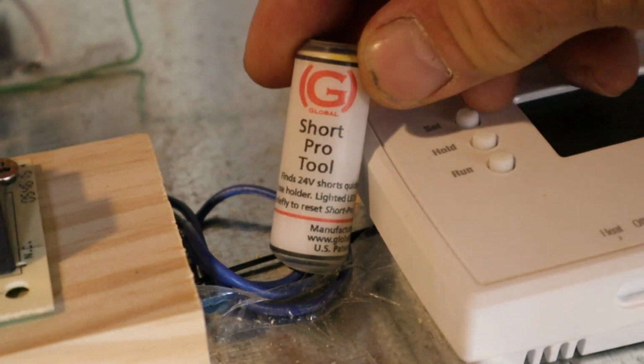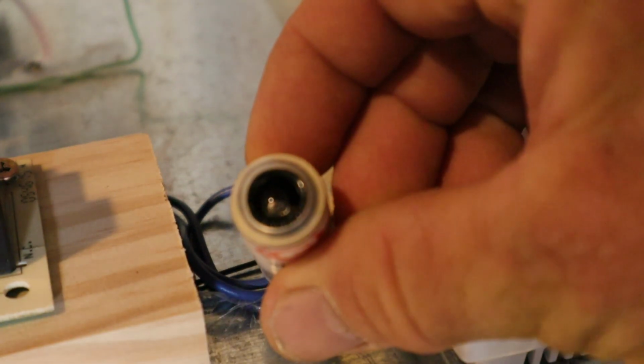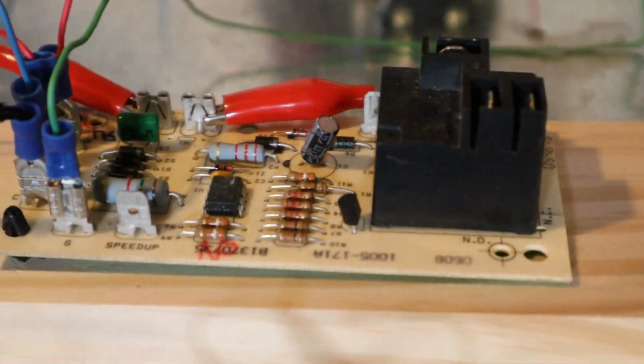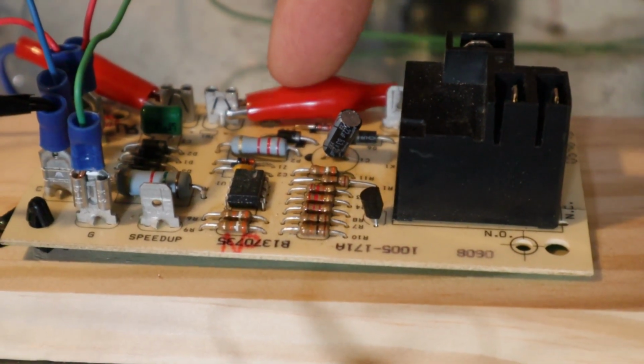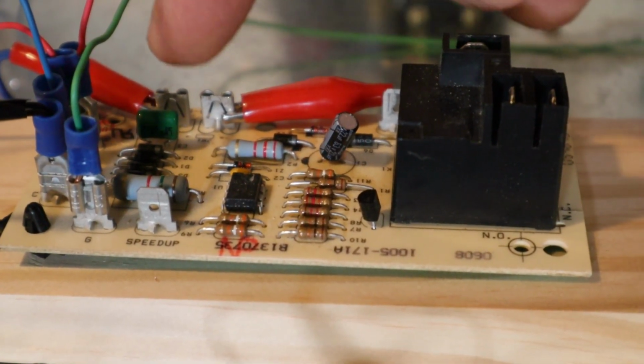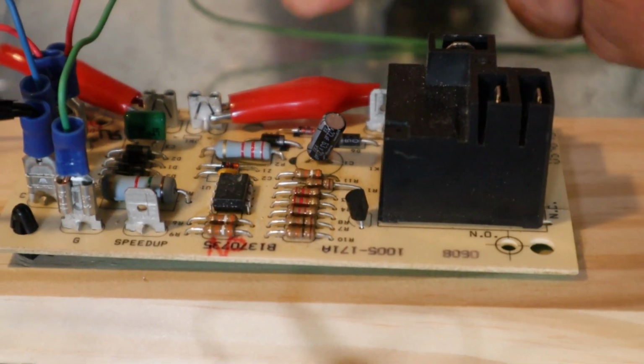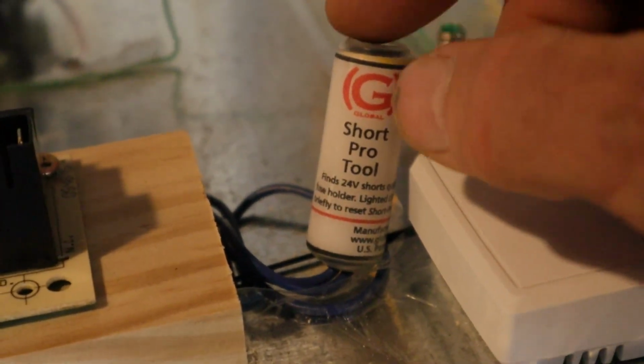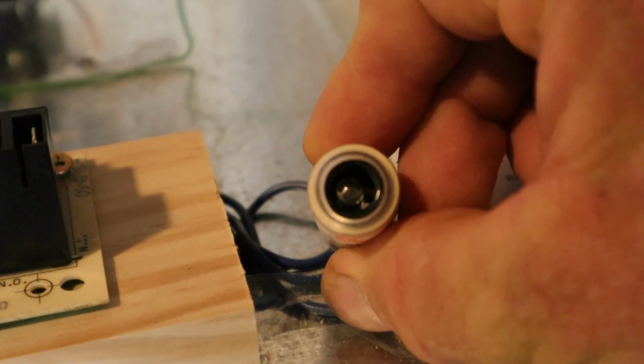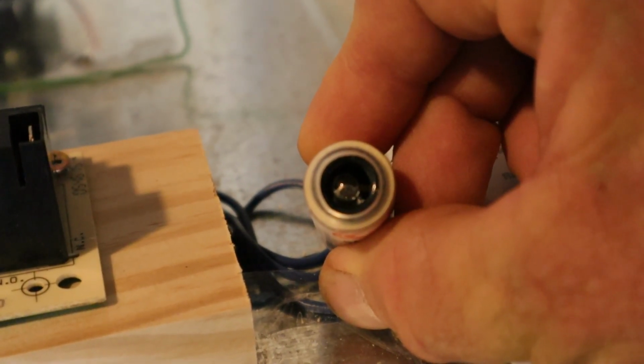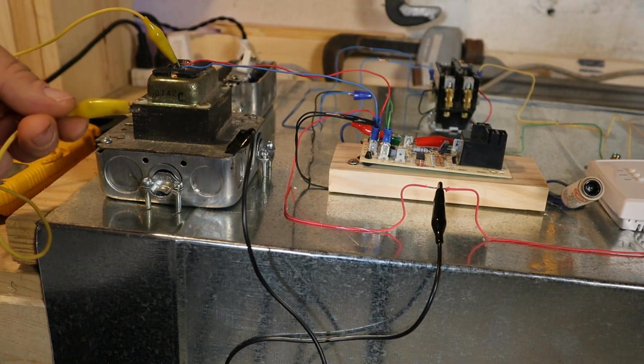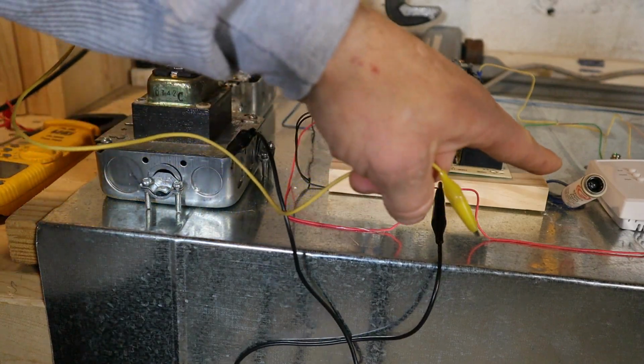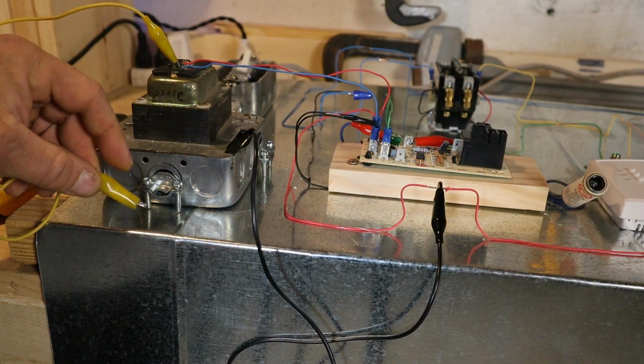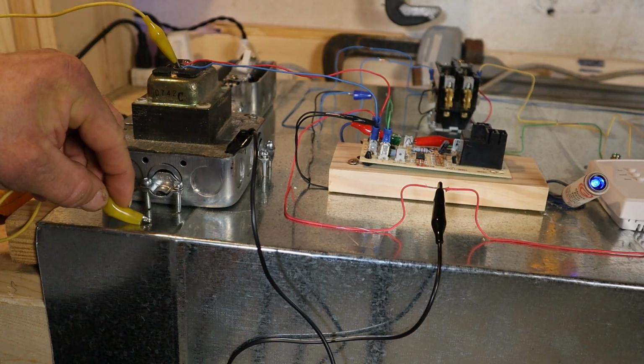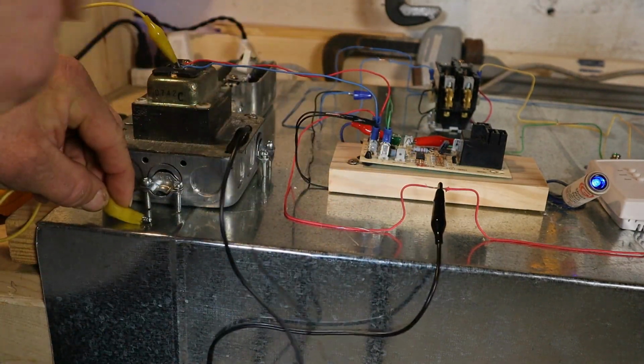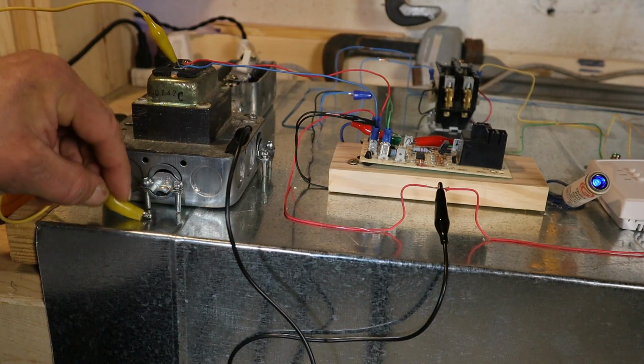So what I have here is what's called a Short Pro tool. It has a little light on it, and what you do is you connect the alligator clips to where the fuse might go on a control board. So we take our fuse out, we hook our clips up, and if we have a short, there's a little blue light on top of here that will light up, telling us we still have a short. If there's no short, it doesn't light up. Now I'm going to ground this secondary and keep an eye on our Short Pro tool. As soon as I touch to metal, you can see we now have a short, because now we have a path for that voltage to make its way back to common. Short, no short. Short, no short.